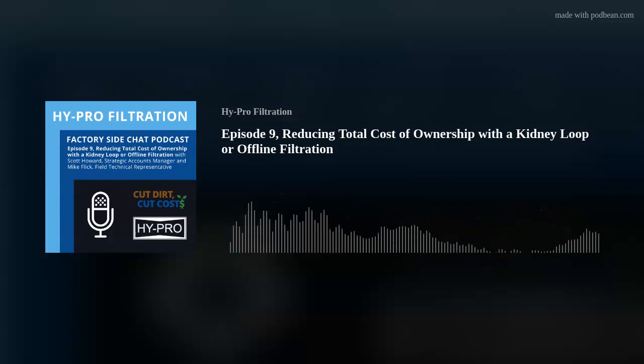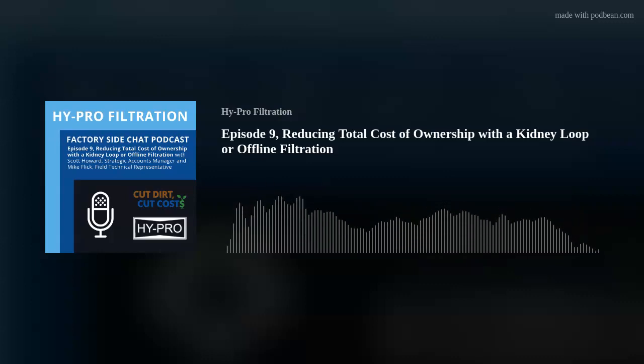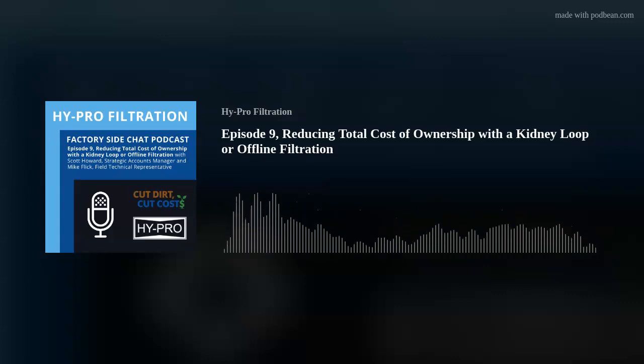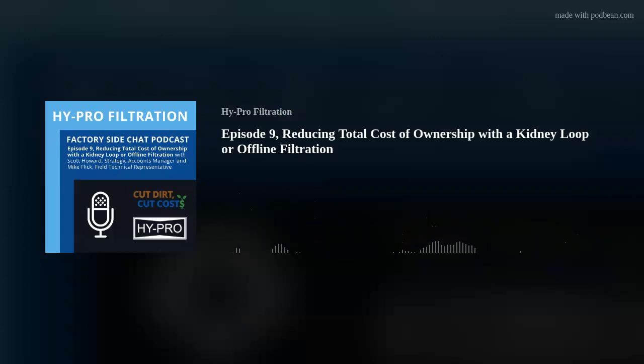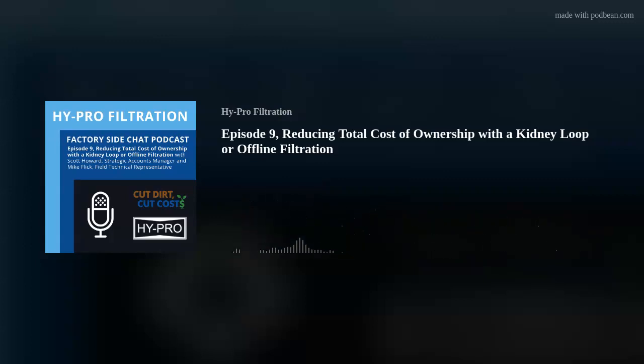Any final comments on kidney loops or offline filter units, Mike? I can just say that I have several customers that have ISO code targets in the industry of 16/14/11 or 16/14/12. And every time we've added an offline kidney loop or they use a filter cart, they are well below their target and are heading towards servo quality oil.